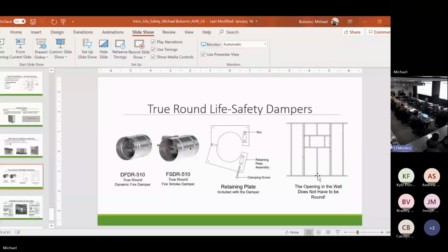They're more cost effective, easier to install, and could be up to 85% lower pressure drop compared to a multi-blade with the square round transition. The framing is the same for a square damper and a round damper. The hole in the sheetrock is the same. It's square. I cut this template, and this retaining plate takes the place of a retaining angle. We have an embossed square template on it that matches the requirements of UL.